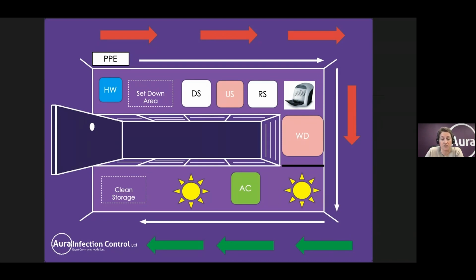So if you use a type 1 indicator on the side of a pouch, or if you've put a TST strip in there, we are also checking and signing off to say that those parameters have been met. Again, a magnification lamp should be used to aid the visual inspection of each of the items. We're still looking for damage, for retained soil. It's your second opportunity to make sure that nothing is going to get put into storage that shouldn't be.